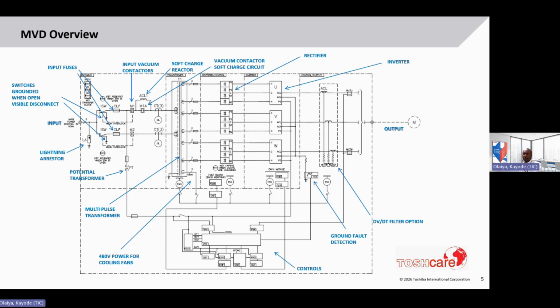Then we have the multi-pulse transformer, which provides power to rectifiers and the rest of the drive, and also has a tertiary winding that provides 480 volts to the drive cooling fans. We talked about the rectifiers. Those are connected to the fused secondary of the transformer, and then connected to the inverter section, which consists of the power modules. On the output of the modules, there is a ground fault detection board for sensing ground current, and there are options for filtering of the output, such as a sine wave filter or a dv/dt filter. And before that we have Hall CTs, which sense current.